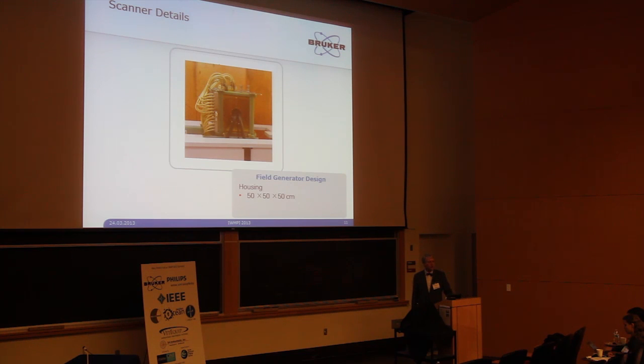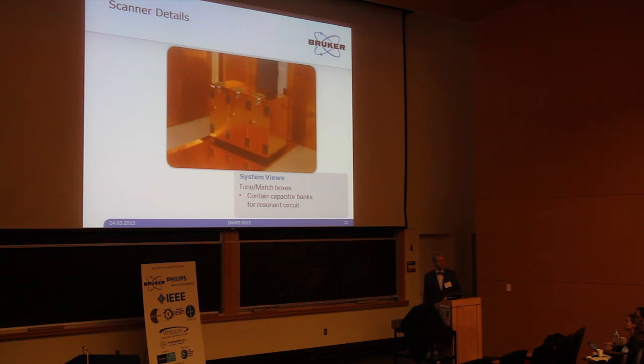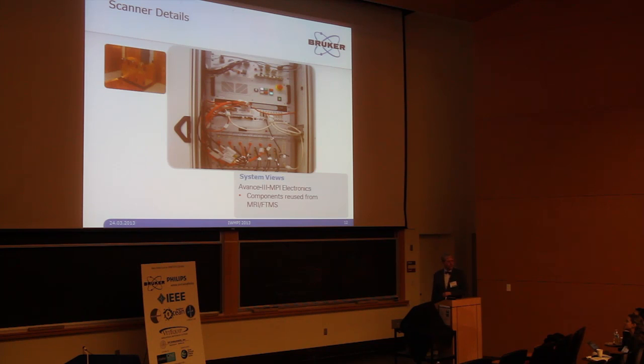And this is what it looks like in reality, installed on the scanner. Some more details: as I said, everything needs to be boxed and integrated into compact components. Here you see these boxes that contain the actual resonance circuits, very compact, just a single box that houses all the components, lots of capacitors, coupling circuits, and filters, and so on. Here's the electronics, again not very large: the sequence controller, the gradient interface, and the detection rack, acquisition rack.